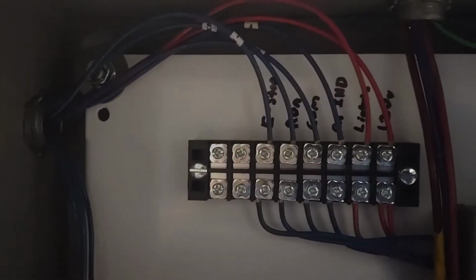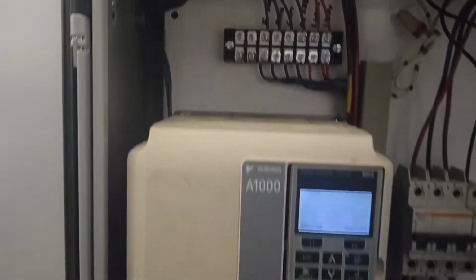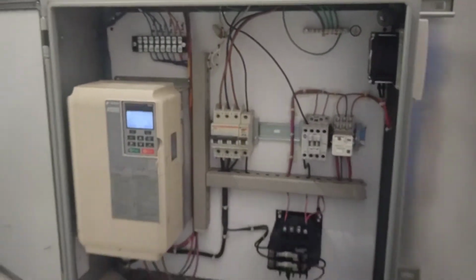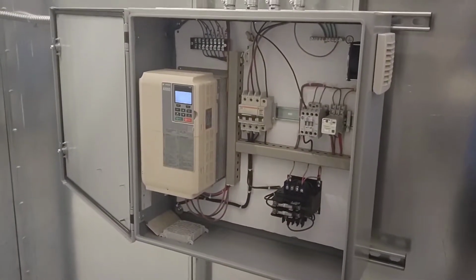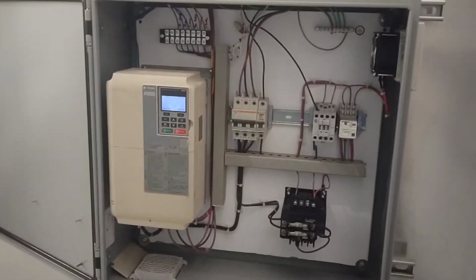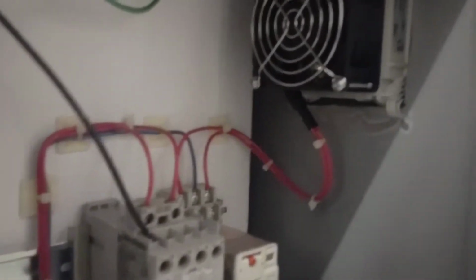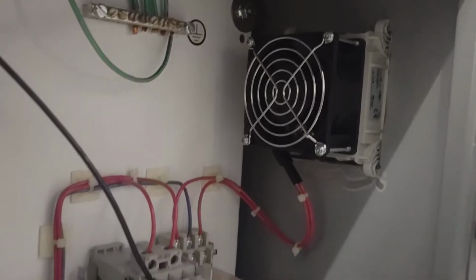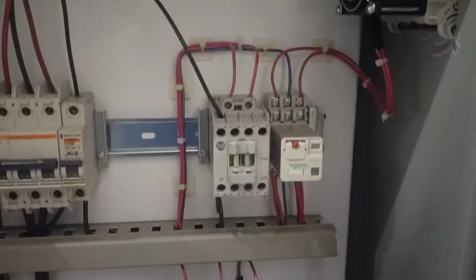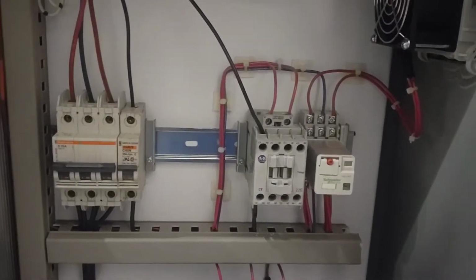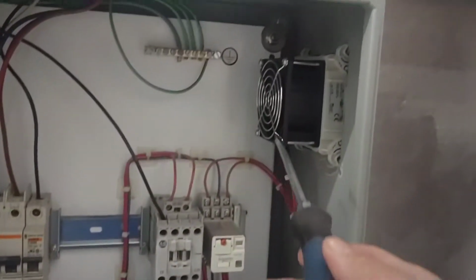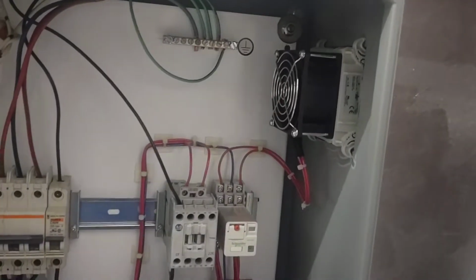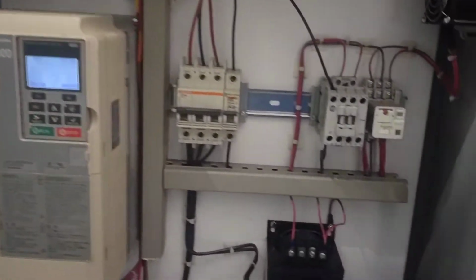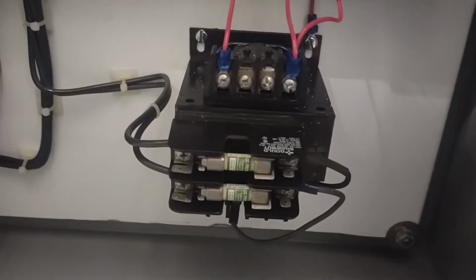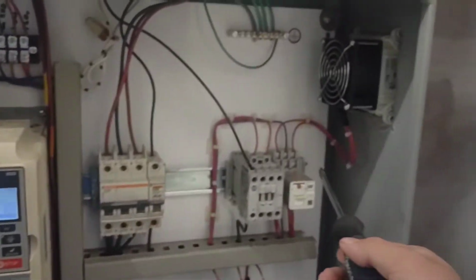Here's my control wiring coming in. Just a simple little panel. Neat, gets the job done here for the shop. So you can see we've also got an exhaust fan, very important. The relay will come in when the drive is in run mode, and that will turn our fan on and also turn our run light on the front panel where we have our controls set up. And then we just have a little control transformer here, which is just for the relay and the fan.